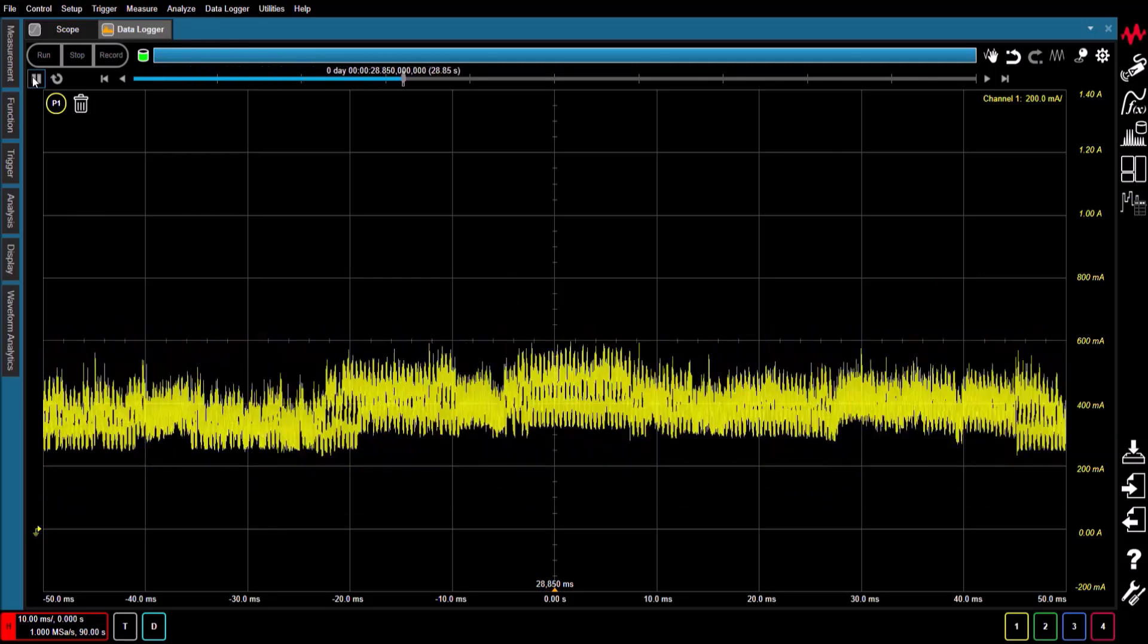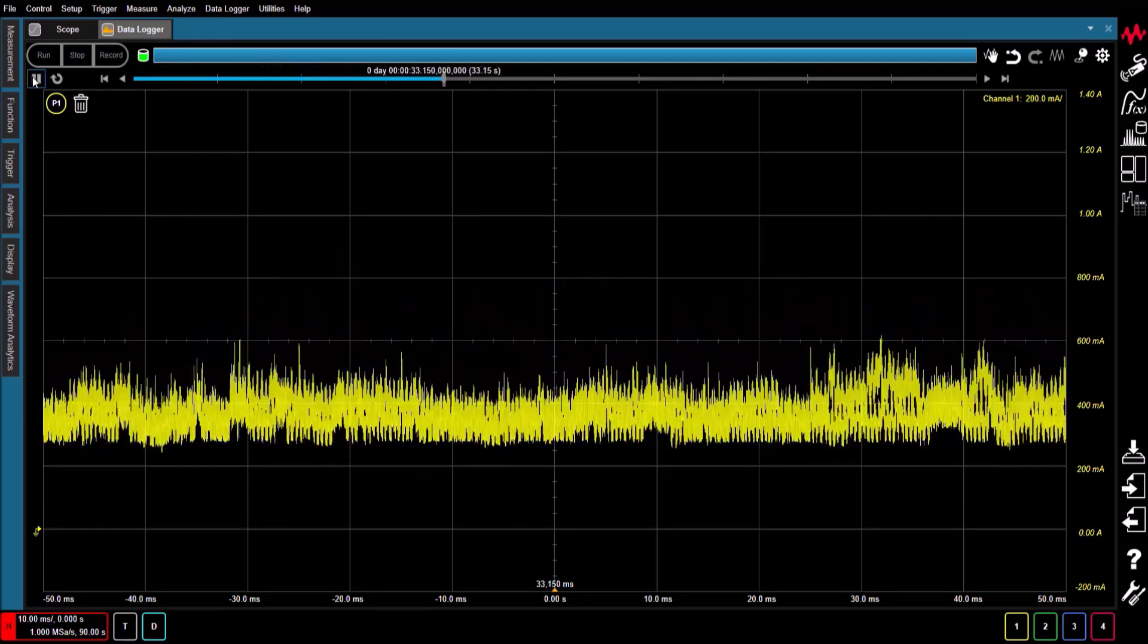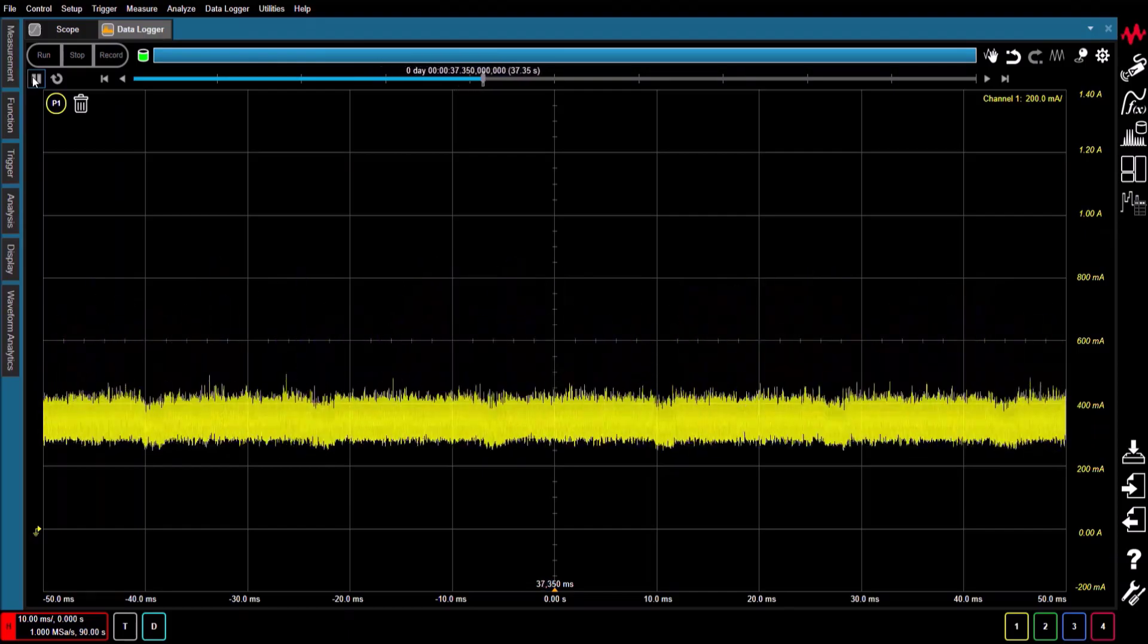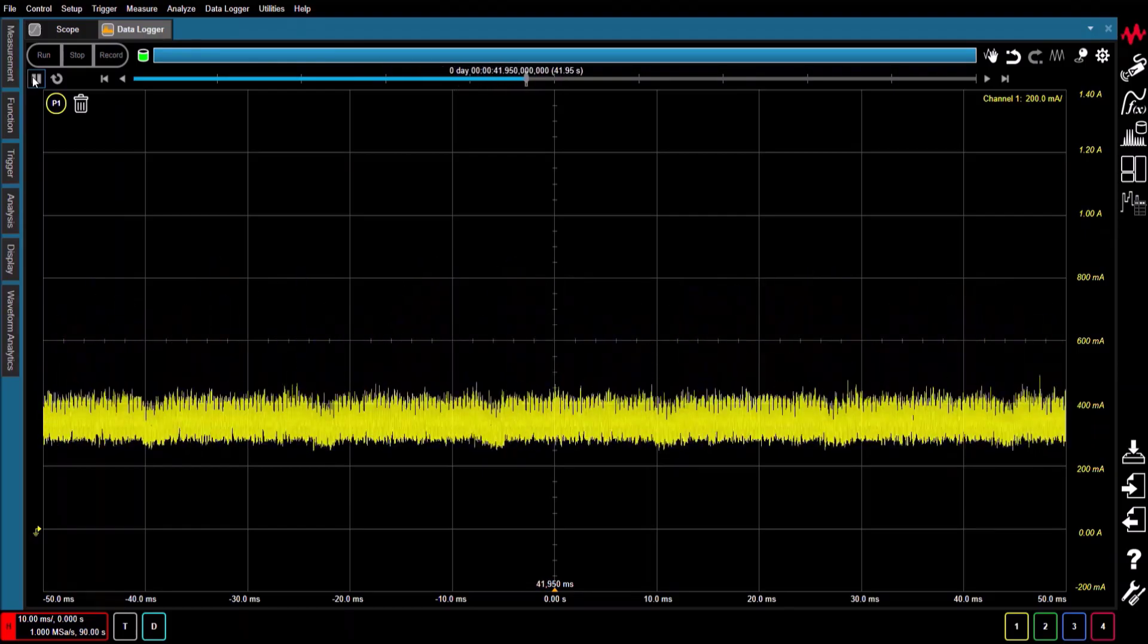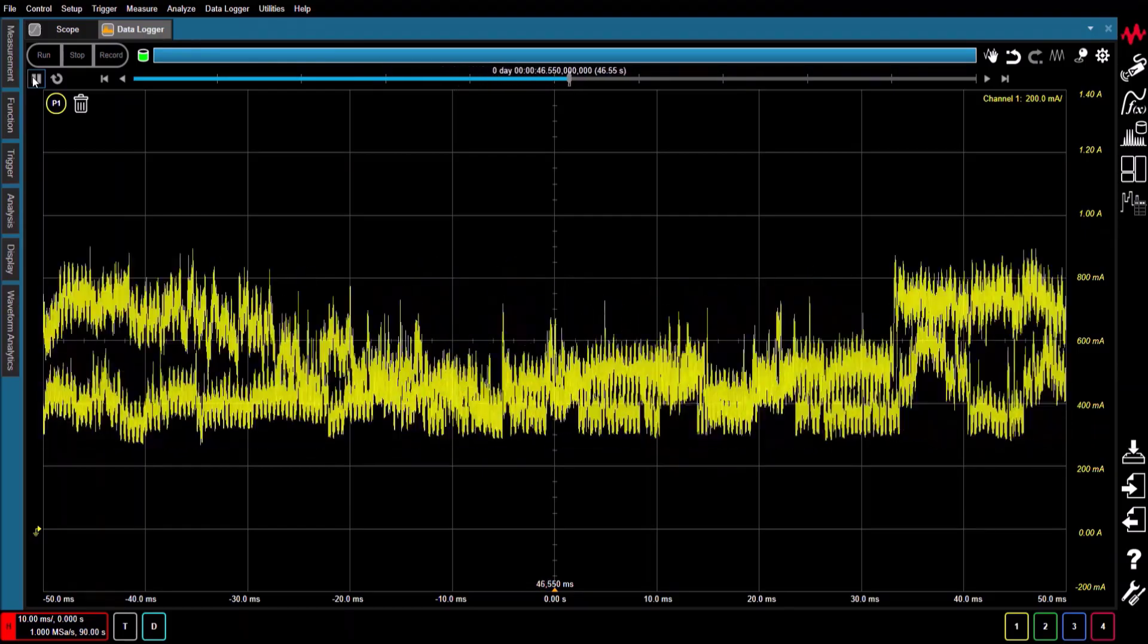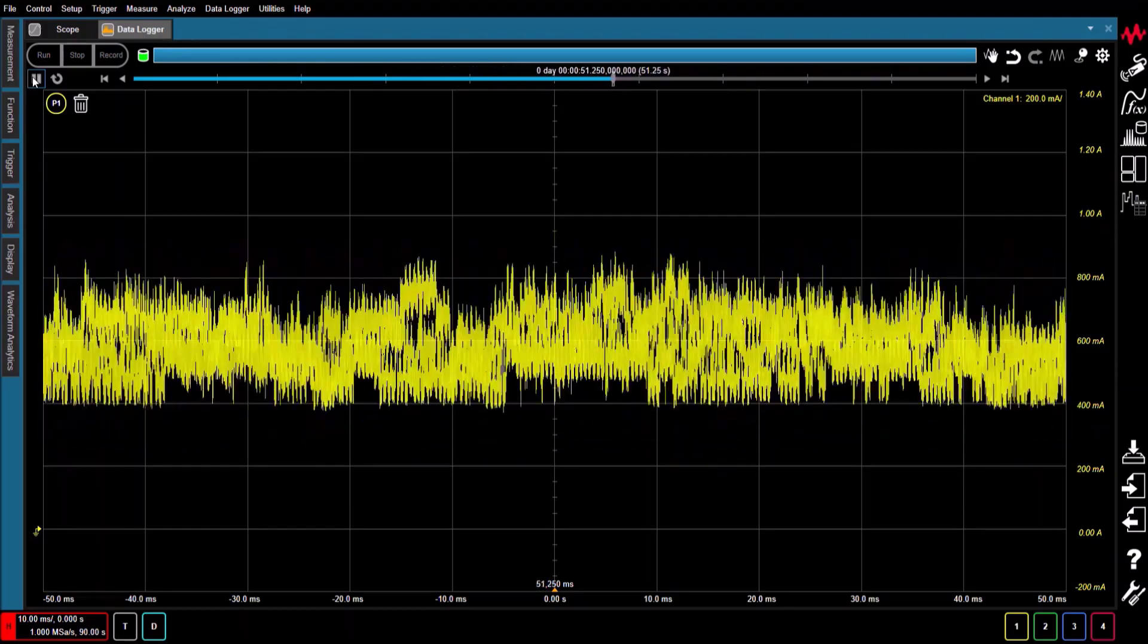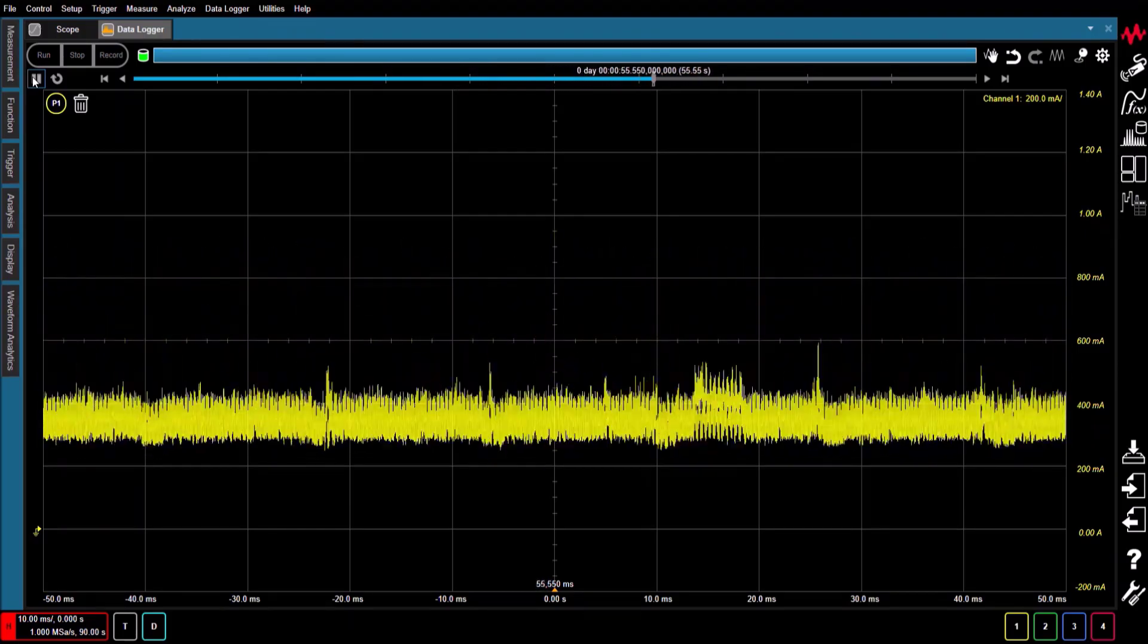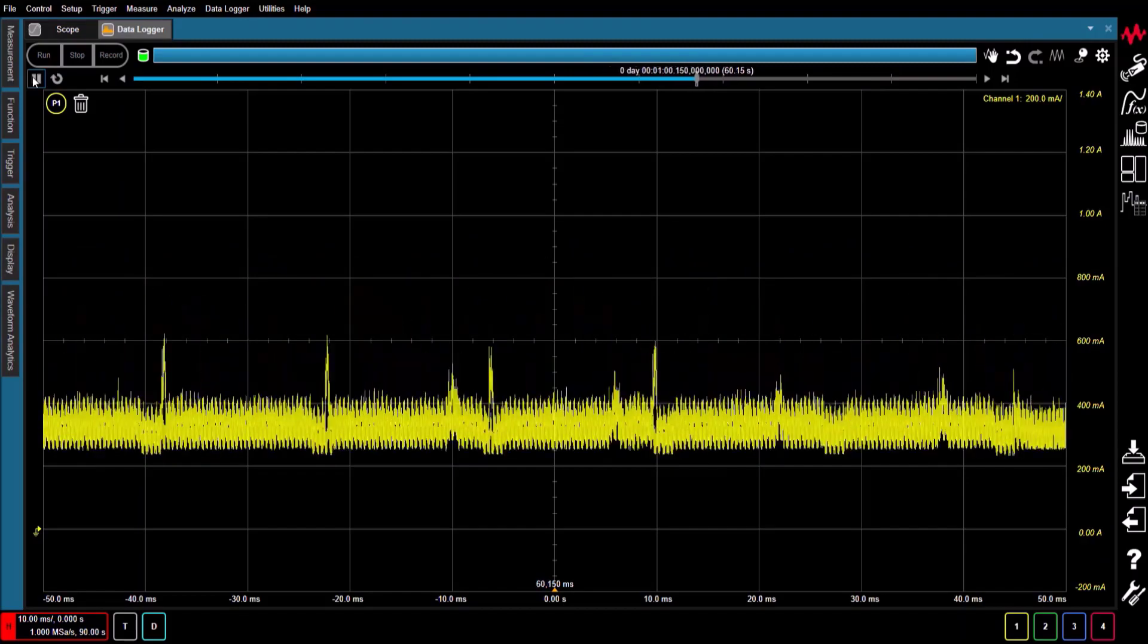The data shown here is an operating system, or OS, startup current waveform that was captured at one mega sample per second for 90 seconds.